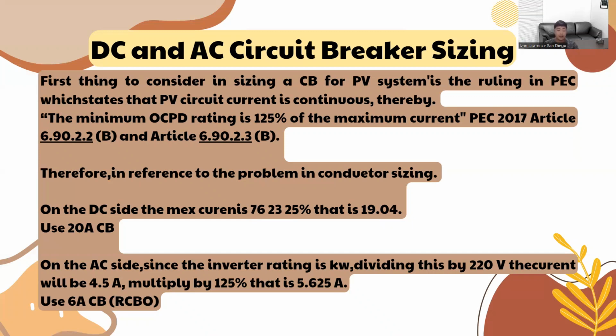Use 20 A CB. On the AC side, since the inverter rating is in kilowatts, dividing this by 220 volts, the current will be 4.5 amperes. Multiplied by 125%, that is 5.625 amperes. Use 6 A CB or RCBO.